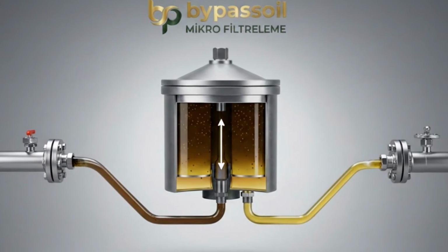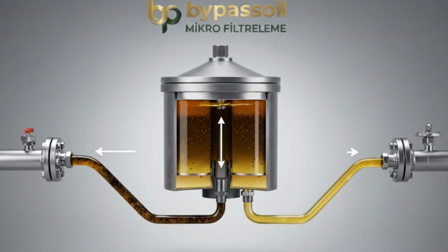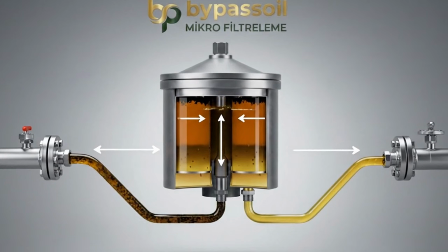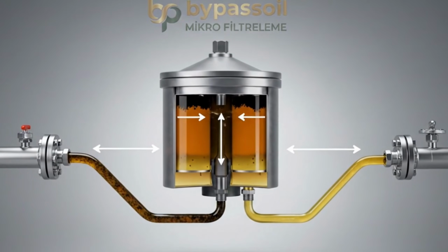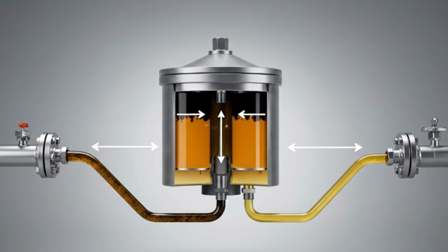The Bypassoil microfiltration installed in the bypass circuit removes harmful contaminants by filtering them out or retains them by absorbing them into its cellulose structure. For this reason, it is extremely effective in system cleaning.